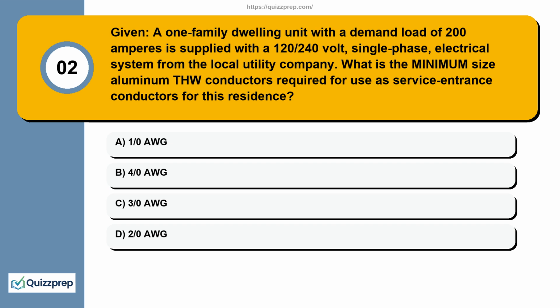Question 2. Given, a one-family dwelling unit with a demand load of 200 amperes is supplied with a 120/240 volt, single-phase, electrical system from the local utility company. What is the minimum size aluminum conductors required for use as service entrance conductors for this residence? 1/0 AWG, 4/0 AWG, 3/0 AWG, 2/0 AWG.